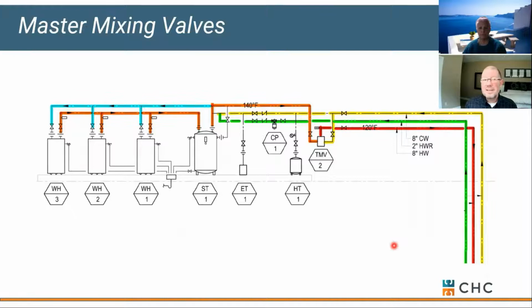The issue is it's taking individuals 10 minutes to get hot water when they wake up in the morning, okay? That's a long wait for a shower, and people are getting a little upset with that, okay? So everybody's wondering what to do. So send me a flow schematic. Let's look at it. So what you've got here is the yellow line is cold water supply, okay?